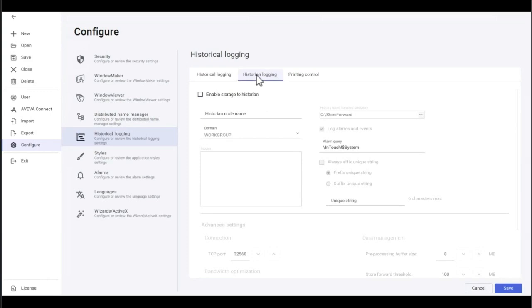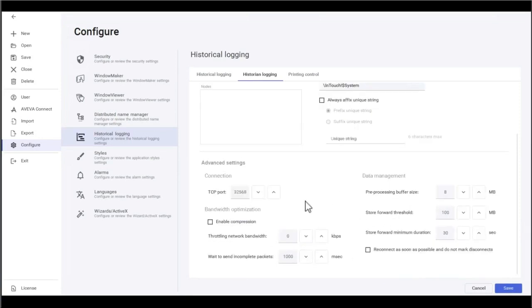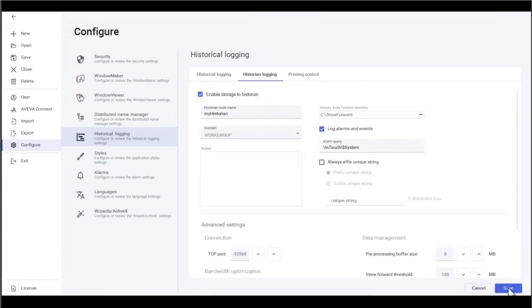But now I can go in and say I want historian logging. When I select historian logging, I simply type in the name of my historian, and over here I can set my store and forward directory. If I'm on a workgroup or a domain, I can select that. I can determine whether I want to log all my alarms and events and what group I want to start logging those events at. If I have multiple InTouch applications with the same tag names, I can put a prefix. I've got all the configuration options to optimize it, and I go ahead and hit save.